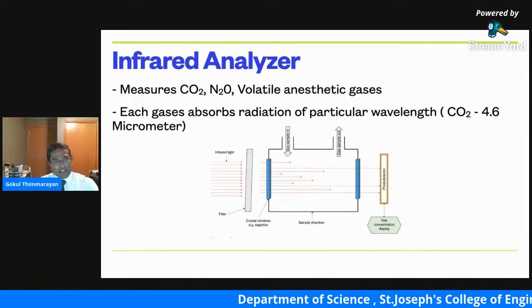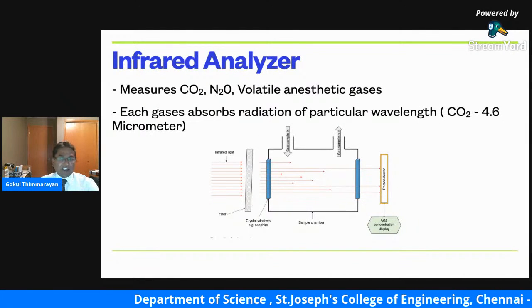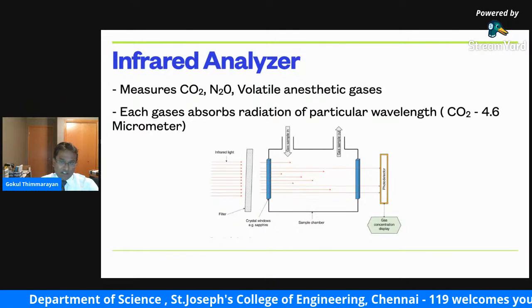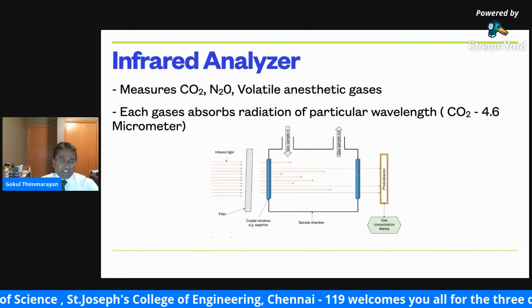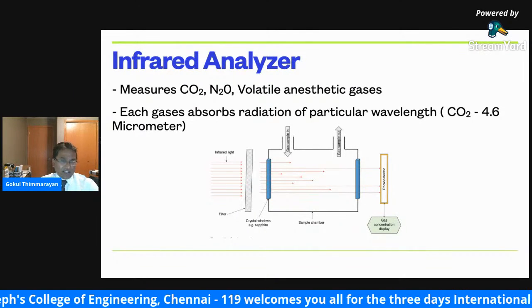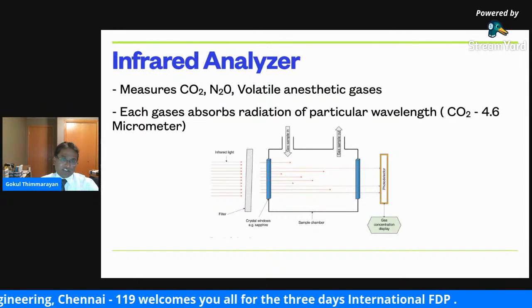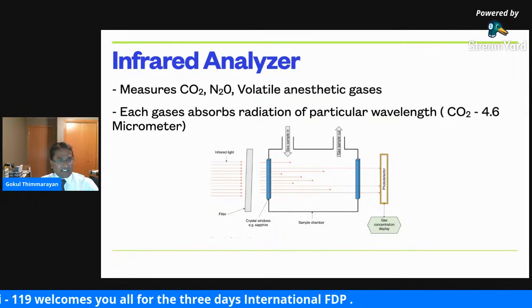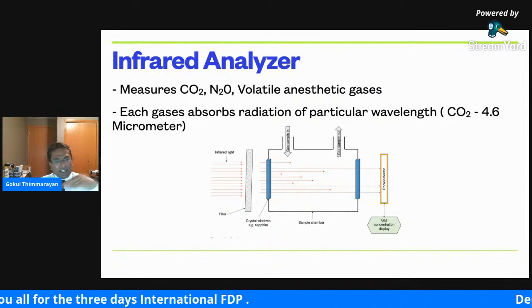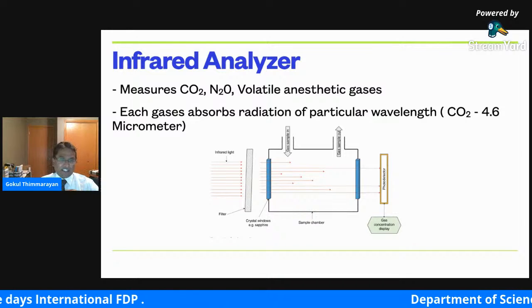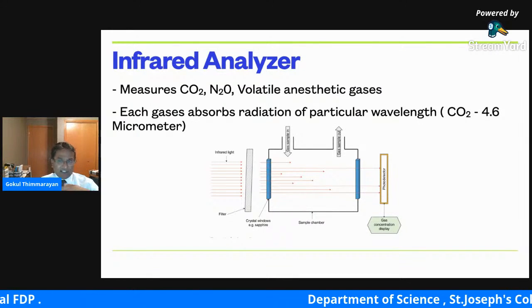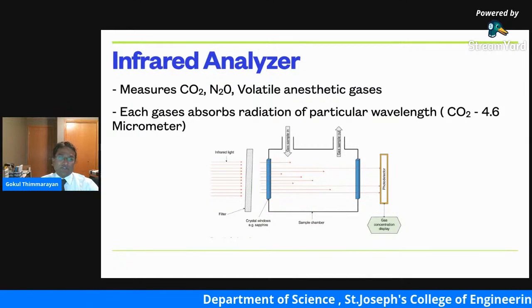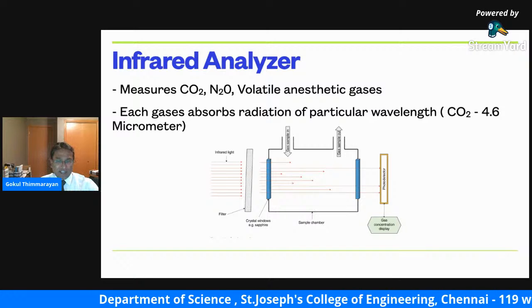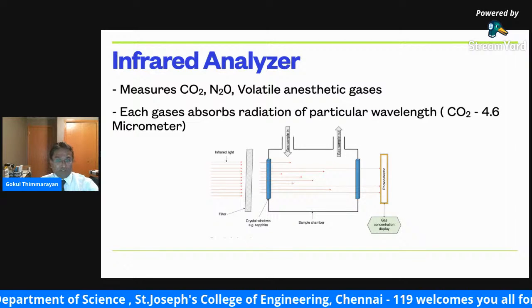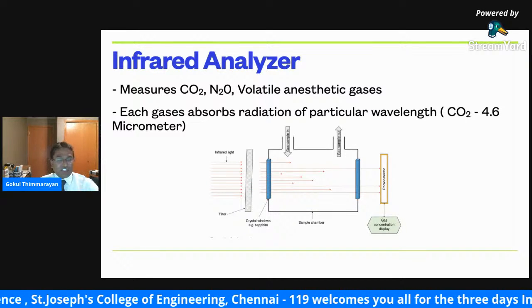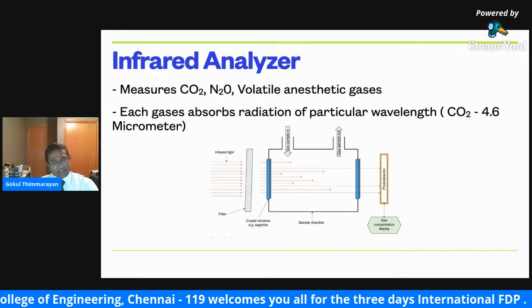And the other method is the infrared analyzer, and it works on the principle of Beer-Lambert's law as well. With this method, we could analyze and identify carbon dioxide, nitrous oxide, and other volatile anesthetic gases. When infrared light is passed through the sample gas and reaches the sensor, the amount of light absorbed identifies the gas and the amount of gas that we are intending to analyze.